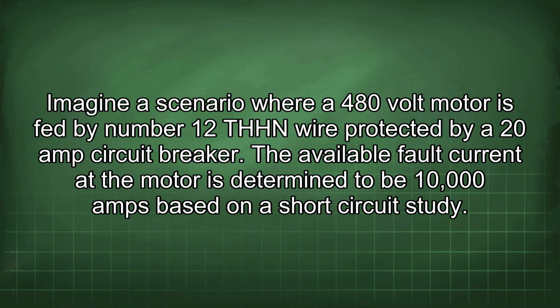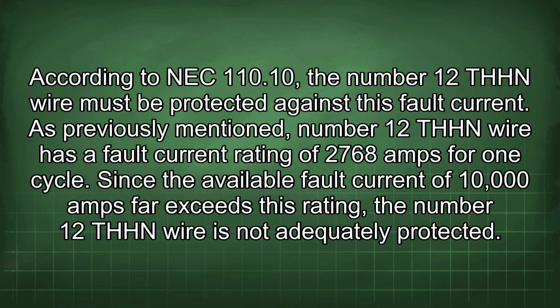Imagine a scenario where a 480-volt motor is fed by number 12 THHN wire protected by a 20-amp circuit breaker. The available fault current at the motor is determined to be 10,000 amps based on a short-circuit study. According to NEC 110.10, the number 12 THHN wire must be protected against this fault current. As previously mentioned, number 12 THHN wire has a fault current rating of 2768 amps for one cycle. Since the available fault current of 10,000 amps far exceeds this rating, the number 12 THHN wire is not adequately protected.